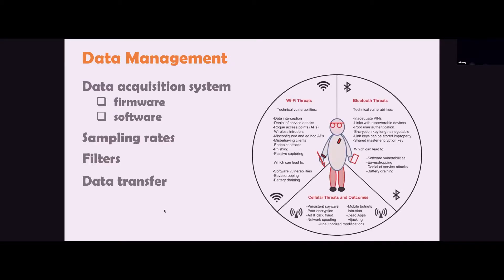Think about data transfer. How do we get the data off the device? Will it use something like the Bluetooth low energy protocols, BLE protocols? If yes, then what is its impact on the battery life? One issue that arises with wearable sensors is that the wireless transmissions from the sensor can pose a security risk for interception and insertion of rogue data if it is not encrypted or protected by other security methods.